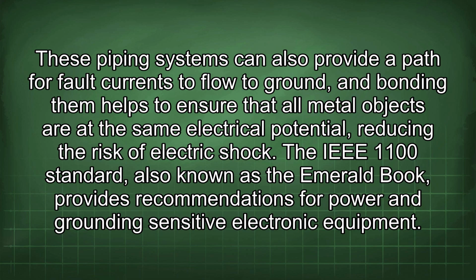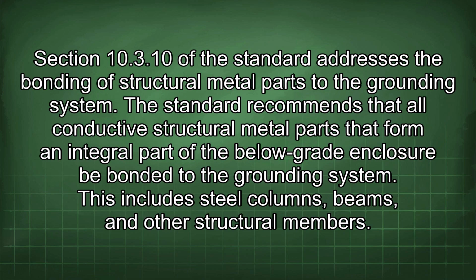The IEEE 1100 standard, also known as the Emerald Book, provides recommendations for power and grounding sensitive electronic equipment. Section 10.3.10 of the standard addresses the bonding of structural metal parts to the grounding system. The standard recommends that all conductive structural metal parts that form an integral part of the below-grade enclosure be bonded to the grounding system. This includes steel columns, beams, and other structural members.